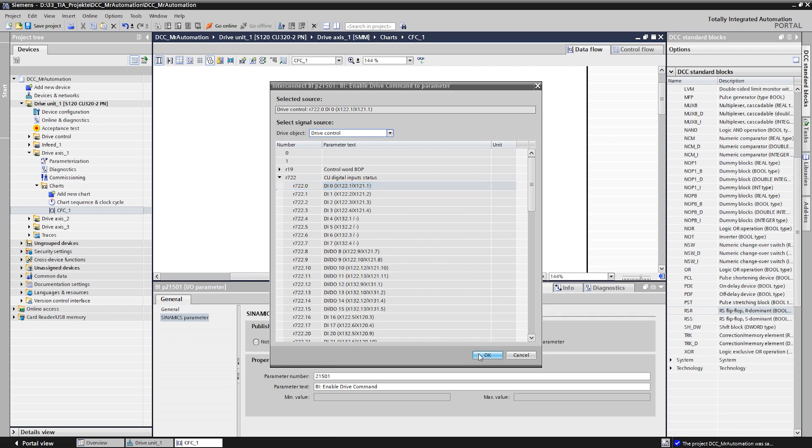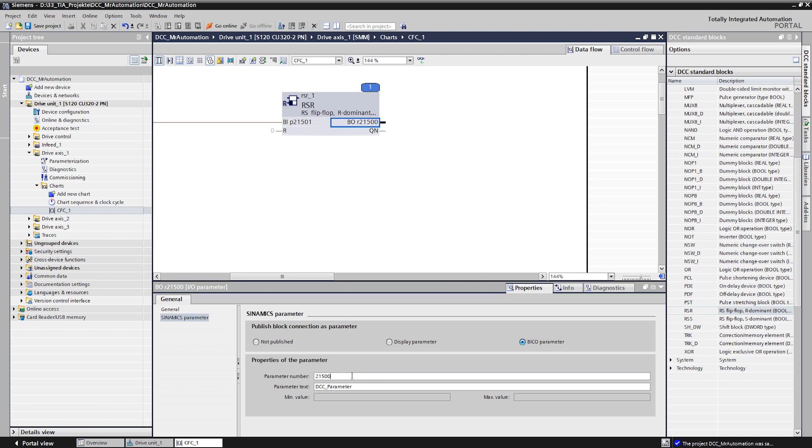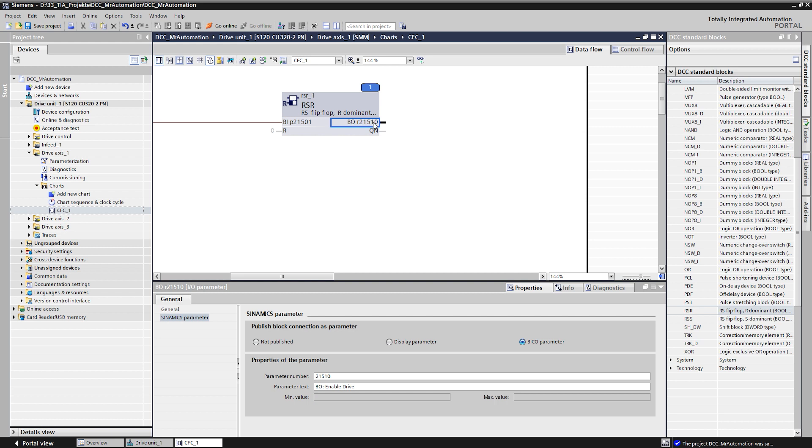In the next step, we want to connect the output signal of the flip-flop to the switch on command of the axis. Also here, the output is published as BICO and given a suitable name. We can now connect the output with the switch on command of the axis which is parameter 840.